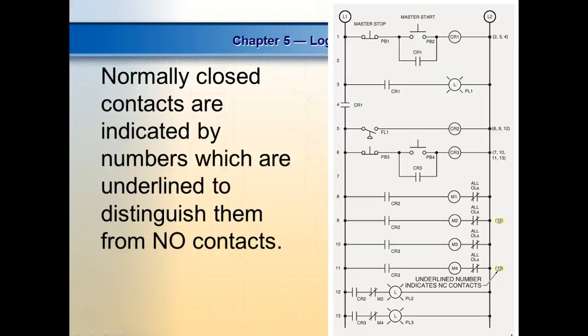I should have done this one, I'm recording this. So this is a control relay, and they're called control relays because the contacts stay in the control circuit. This is a motor starter, so not only might it have contacts in the control circuit, which are auxiliary contacts, it's also going to have contacts in the power circuit.